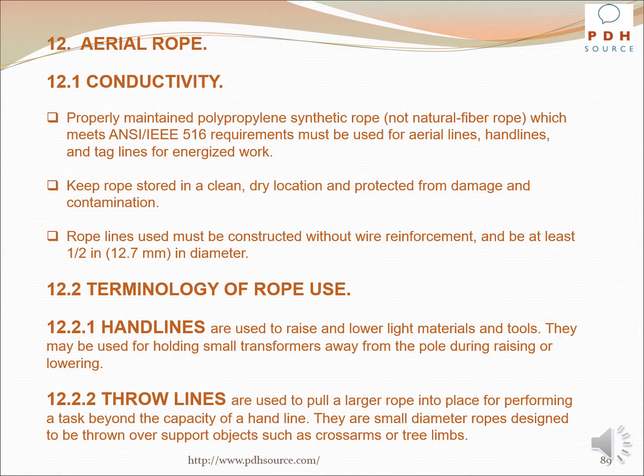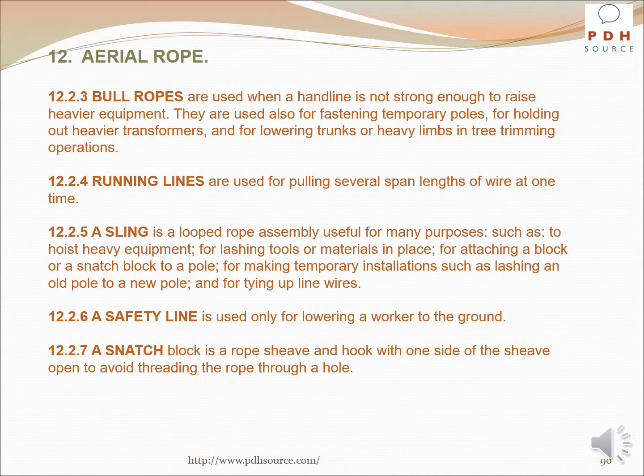Throw lines are used to pull a larger rope into place for performing a task beyond the capacity of a hand line. They are small diameter ropes designed to be thrown over support objects such as cross arms or tree limbs. Bull ropes are used when a hand line is not strong enough to raise heavier equipment. They are used also for fastening temporary poles, for holding out heavier transformers, and for lowering trunks, or heavy limbs in tree trimming operations. Running lines are used for pulling several span lengths of wire at one time.